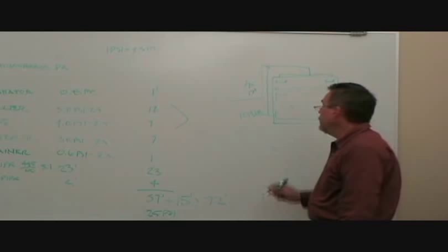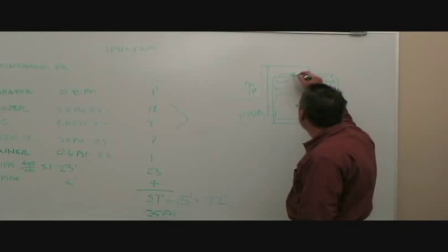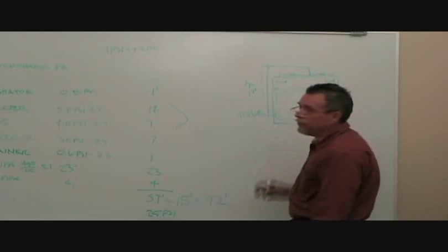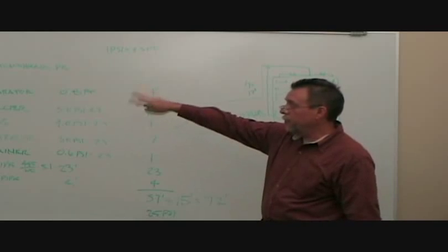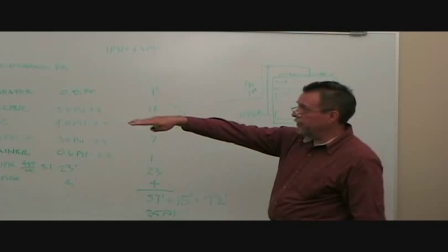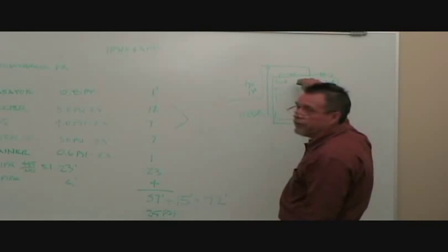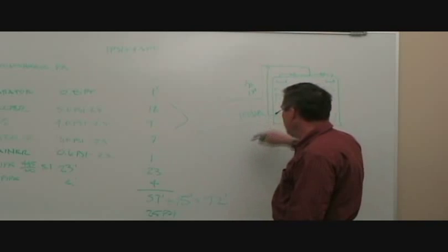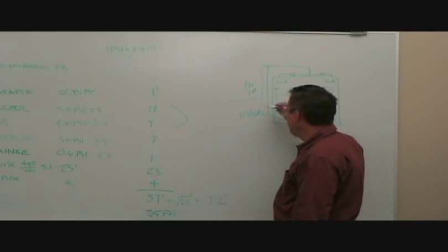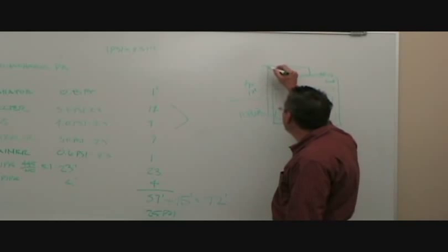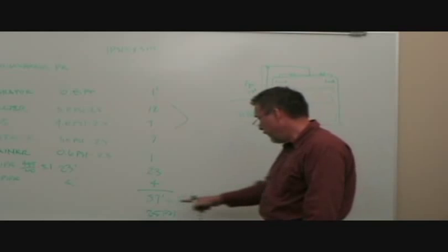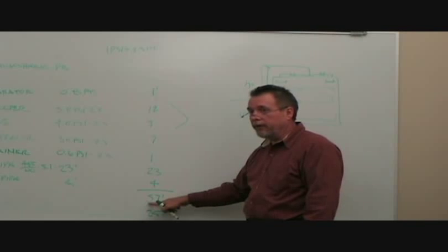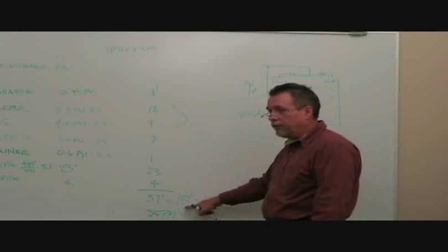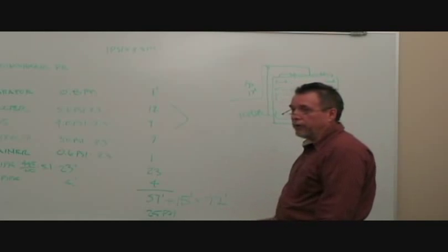Do you take any consideration of your balancing valves on top of your tower? Yeah, you might have some more balancing valves here. They would just figure into your piping loss, same calculation we went through. Got the valves at the chiller, valves at the cooling tower. But since I've got an open cooling tower, I had to figure this H in right here, the lift. So whatever my pipe loss and fitting loss is, add the actual lift for a cooling tower pump.